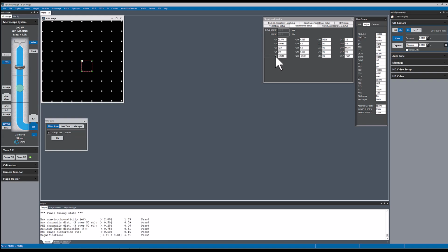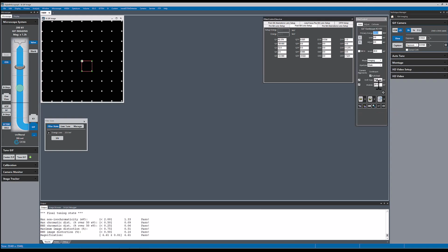If that's not the case, we have chromatic blurring, which is something that we want to avoid. The way that we can use the mask to help us correct for chromatic blurring is to use the drift tube to offset by some amount of eV, and then do what we call a wobble. Essentially we can form two images at different energies.